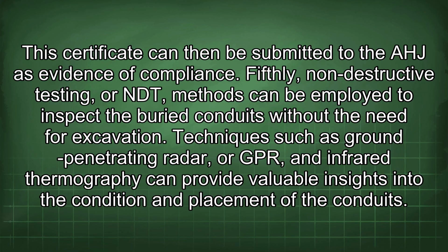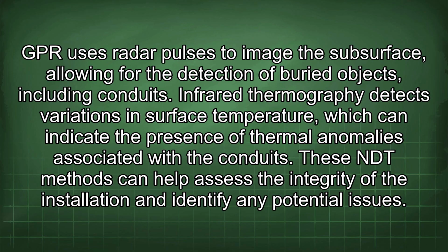Fifthly, non-destructive testing (NDT) methods can be employed to inspect the buried conduits without the need for excavation. Techniques such as ground-penetrating radar (GPR) and infrared thermography can provide valuable insights into the condition and placement of the conduits. GPR uses radar pulses to image the subsurface, allowing detection of buried objects, including conduits. Infrared thermography detects variations in surface temperature, which can indicate thermal anomalies associated with the conduits. These NDT methods can help assess the integrity of the installation and identify any potential issues.